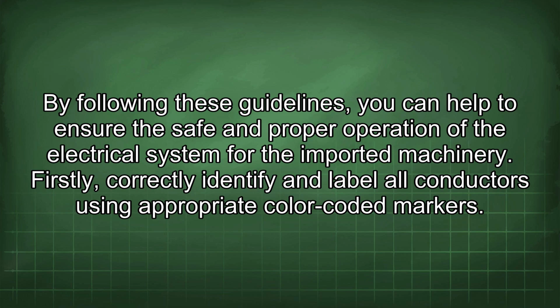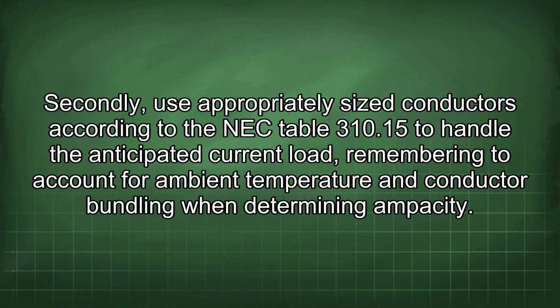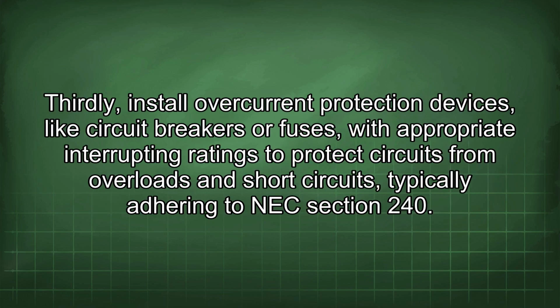Firstly, correctly identify and label all conductors using appropriate color-coded markers. Secondly, use appropriately sized conductors according to the NEC Table 310.15 to handle the anticipated current load, remembering to account for ambient temperature and conductor bundling when determining ampacity. Thirdly, install overcurrent protection devices, like circuit breakers or fuses, with appropriate interrupting ratings to protect circuits from overloads and short circuits, typically adhering to NEC Section 240.